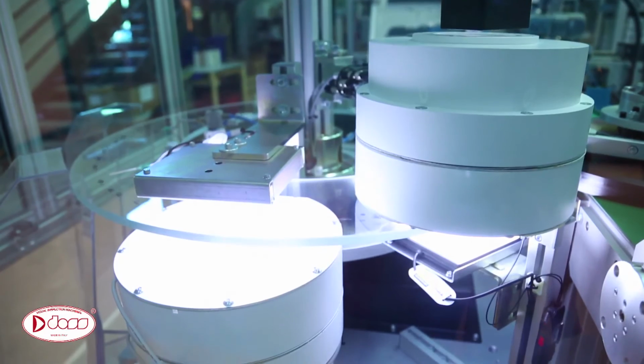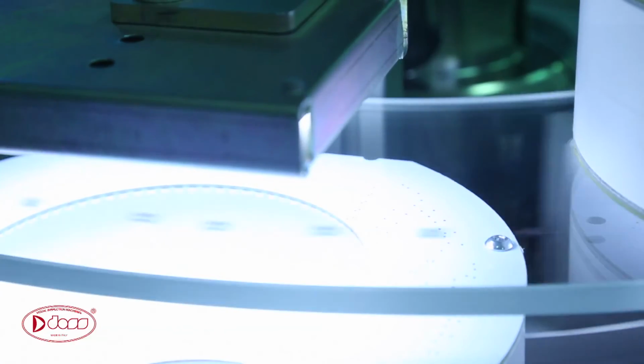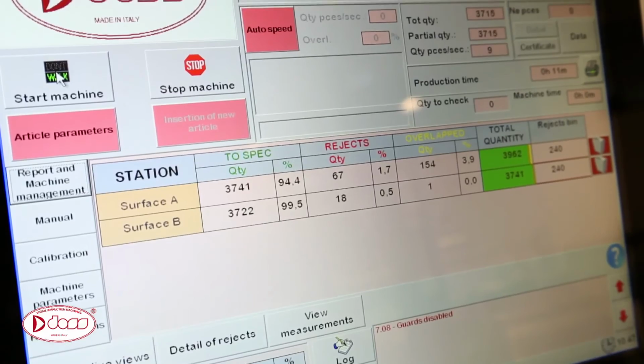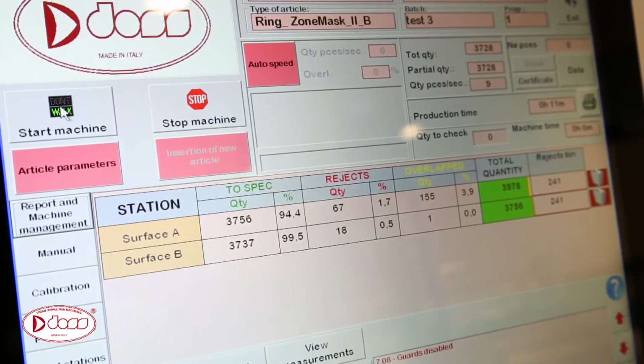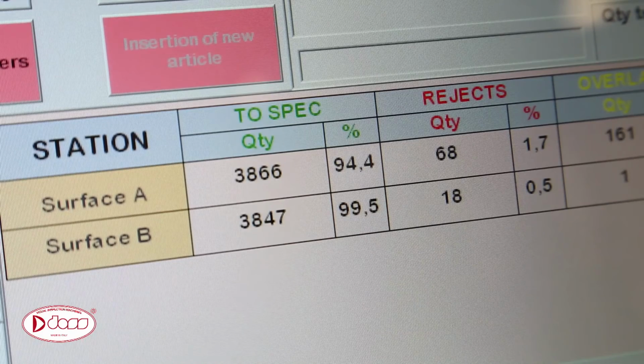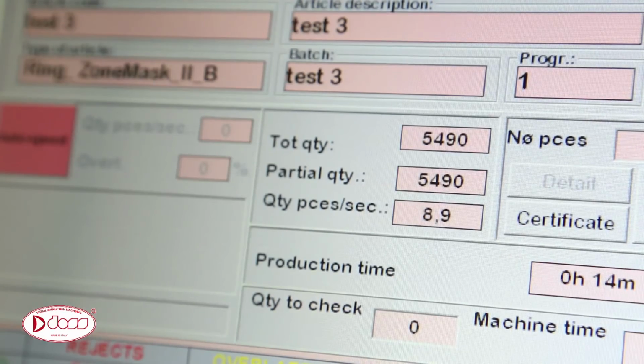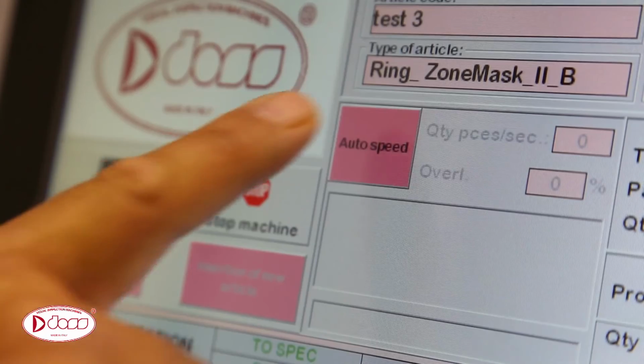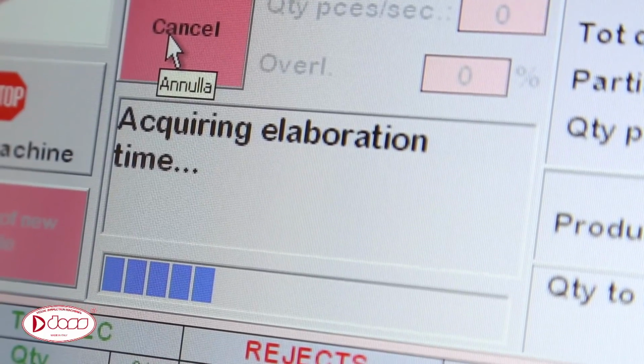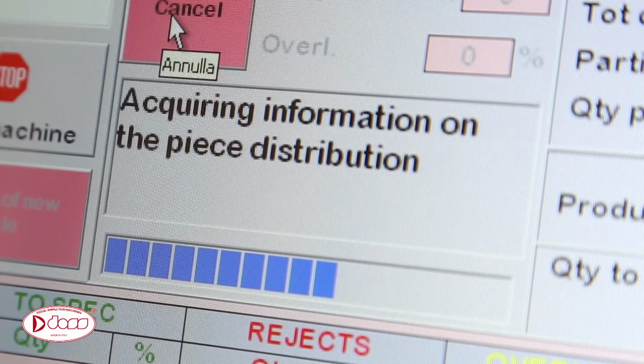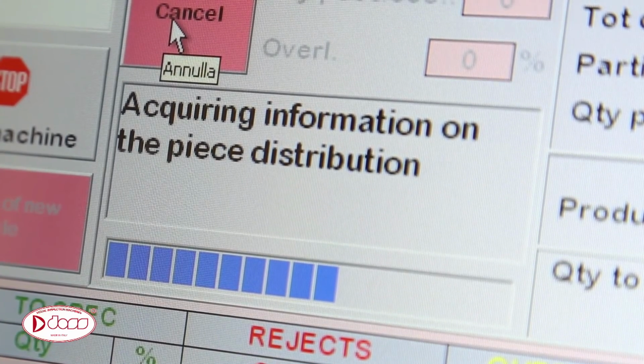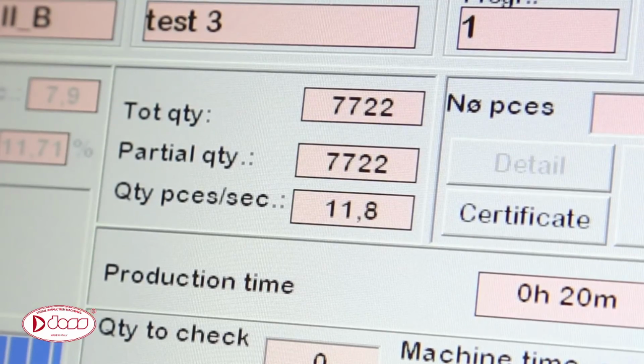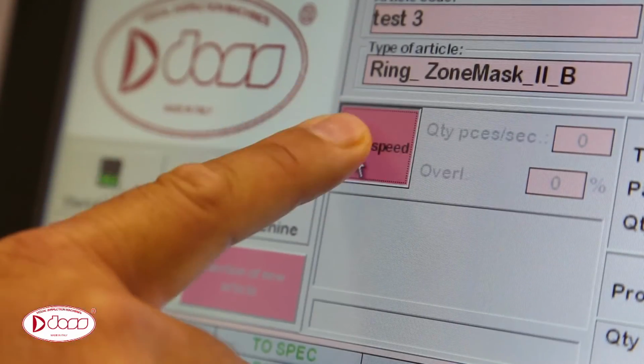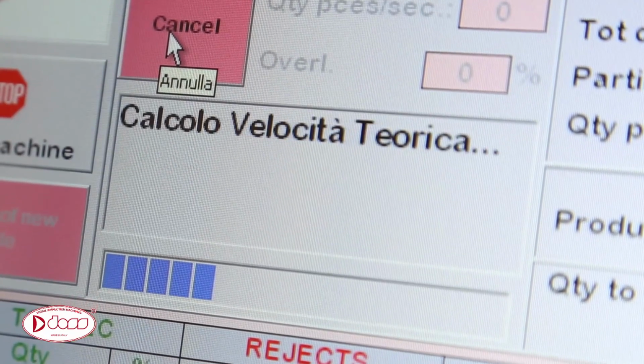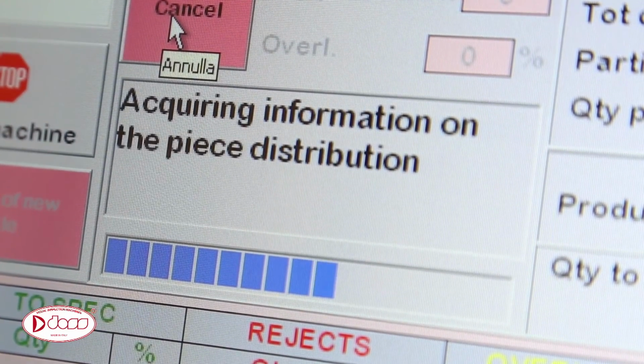Mistral Basic can also optimize your production flow. After starting the machine, you can optimize the speed and run faster with the inspection, even if the parts are made with different materials and different mechanical behaviors. Optimizing and going faster is very easy, by pressing only this button. After a few seconds of collecting data and elaboration of them, the machine speeds up the belts, table, disks, and as you can see now, we are running faster. If you're not satisfied, you can ask the machine to repeat the operation pressing the same button, and the software will do again the calculation, finding the best performance possible for this part.